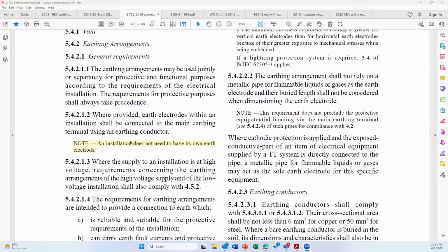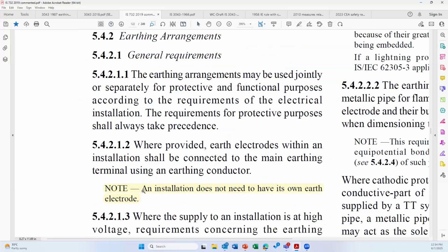Sir, some of the questions are about IEEE 80 as well as about the earth electrode: is one earth electrode enough when all the exposed and extraneous conductive parts are connected, given there is only one earth electrode, which is a danger? For that particular question, I am showing on the screen IS 732 clause 5.4.1. You see here, there is a note: an installation does not need to have its own earth electrode.